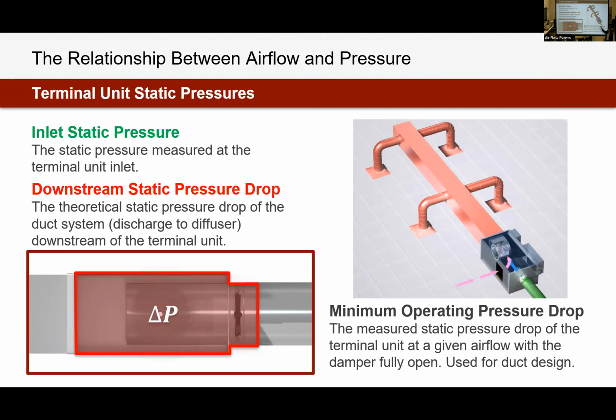inlet static pressure is. Downstream of the terminal unit, so all of the red duct in this image, is where we are measuring or creating a discharge static pressure. All of the accessories downstream of a terminal unit have some sort of resistance to them. Maybe it's straight duct, flex duct, we've got diffusers in this image, could be a water coil, silencer, turning vanes. All these different accessories downstream of a terminal unit are adding resistance to our airflow. The positive pressure that we have on the inlet has to be larger than all of the downstream pressures to get any air to flow down into our space.